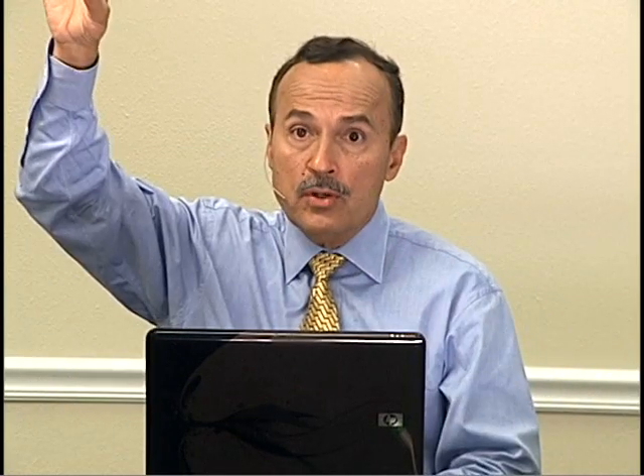Okay, I can say I got circuit conductors right there. I can just tap off of my motor circuit control with 12 gauge wire and I'd be up to 60 amps. Once you get past a 60 amp branch circuit short circuit protection device, now you're going to have overcurrent protection for those conductors, and there's a couple ways to do it.